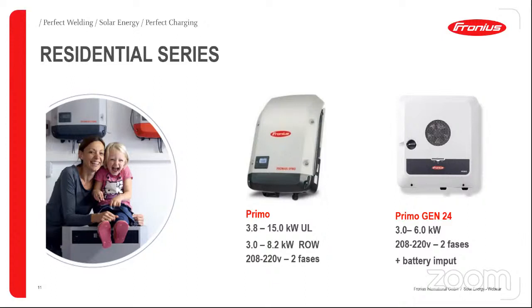One very important thing to consider here is that some countries, like the Dominican Republic and some others in the Caribbean, use 110 volts between phase and neutral. So in those countries, we need to use two phases to connect the inverter, but we are allowed to connect in that way. And the inverter that you see on the right side is the Gen 24 inverter. This is our new device. It's a hybrid inverter that I want to show you later on.